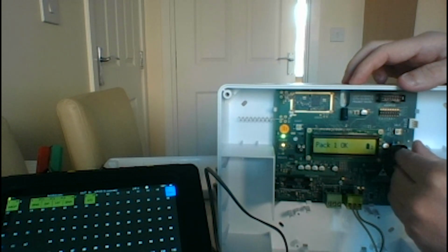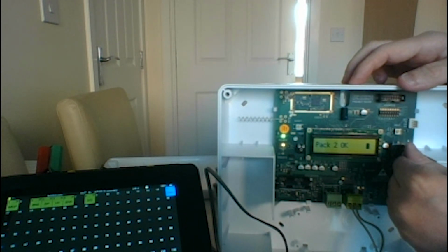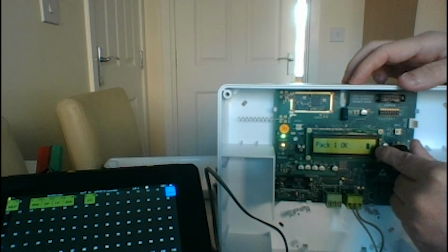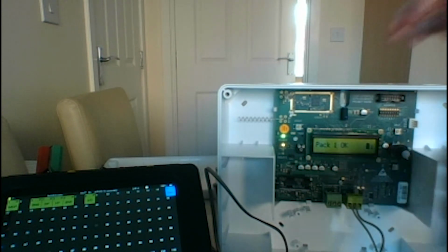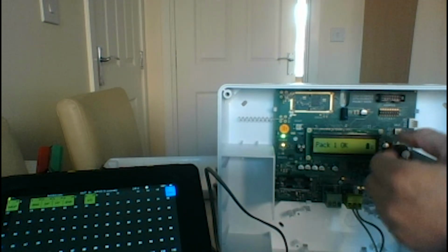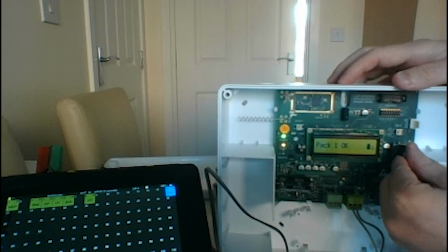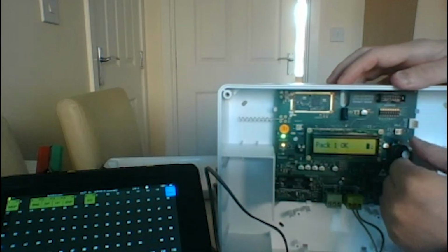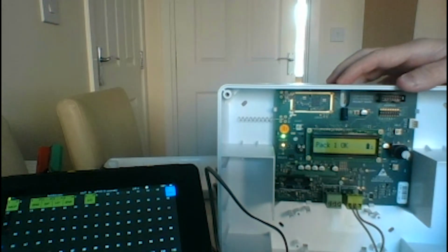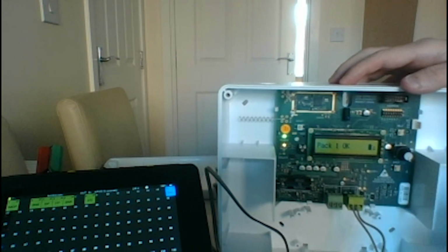These icons aren't exact measurements of the battery. They will show us a full battery in most cases. If that battery icon is half full, then that would be the 30-day warning of the detector that the batteries are going to run out, and you would get an information for that in the main panel. And if that was completely empty, then obviously our batteries are completely gone, and we would get a signal for that as well.